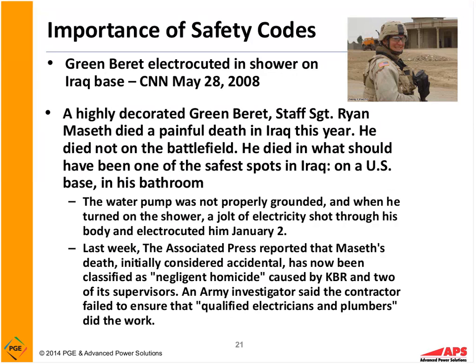So, going over an example of the importance of safety codes here, we see a Green Beret, and I hate to use this as an example, but I've got several examples across the U.S. I could give you hours of examples. Here's a highly decorated Green Beret, Staff Sergeant Ryan Masseth. He died in the bathroom. He reached up and touched the shower handle, and the water pump that was feeding the piping system that fed the showers was not properly grounded and was not properly bonded, and he was electrocuted. He died in the bathroom.